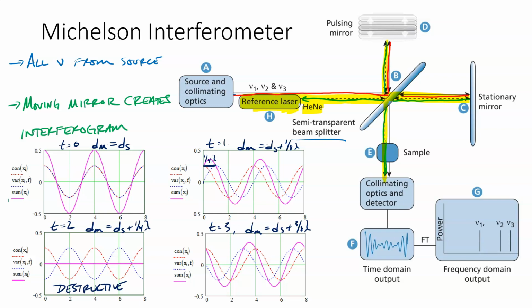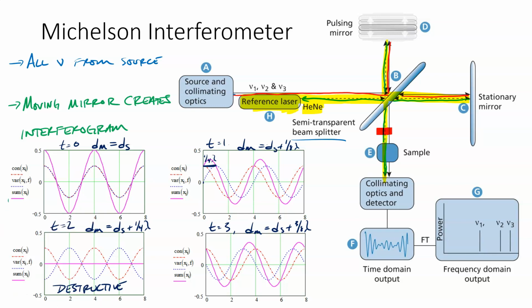Now sometimes that detector is separate from the sample detector, sometimes it's not. In the instrument that we have at Wofford, the detector for the reference mirror is actually about here, right? It detects it just before it goes through the sample. But anyway, what that does is it creates an interferogram of just that HeNe wavelength, and based on the intensity of that light source, it knows the position of that mirror in terms of fractions of wavelengths.